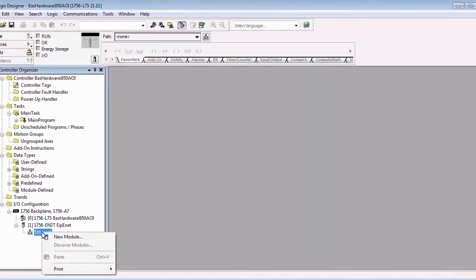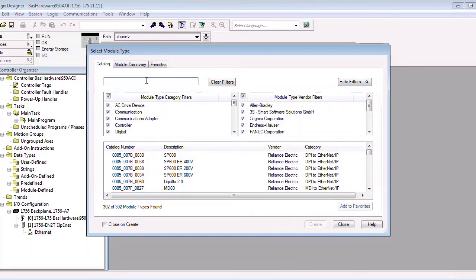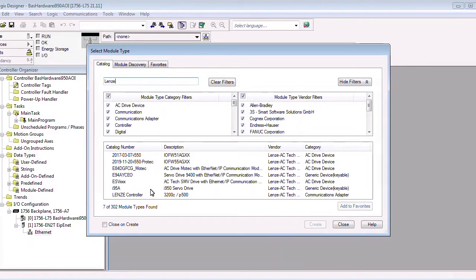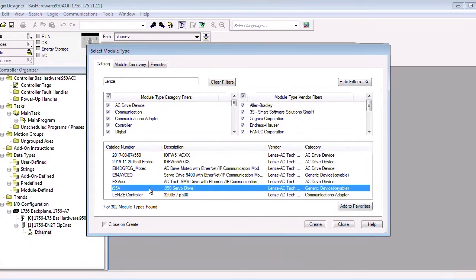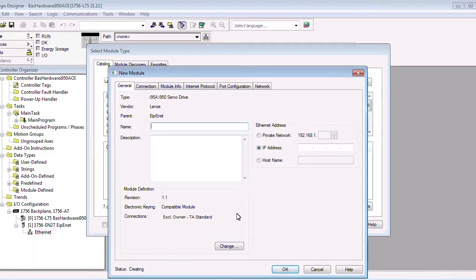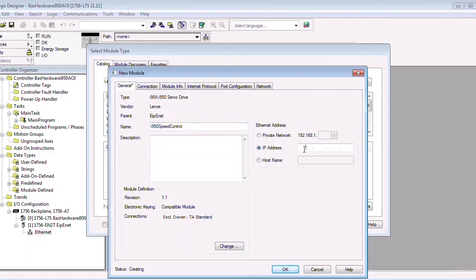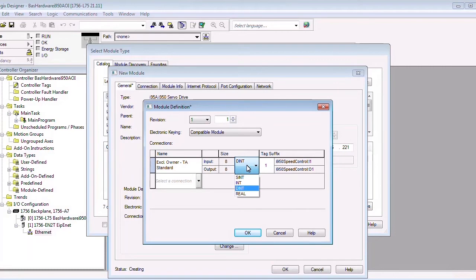Afterwards, if you right-click on Ethernet and select New Module, you'll be able to search for the i950 by typing in Lenze in the search bar to filter down to only Lenze devices. If you double-click on it, you'll be able to edit the properties of the new i950 module. Add in a name for your device and type in the IP address you previously assigned to it. Then click on Change and change the data type to a double integer. Click OK and close the windows once you're done adding all the devices you need.